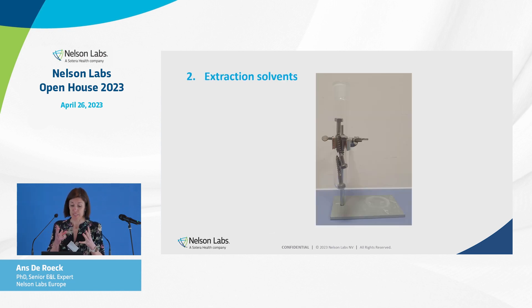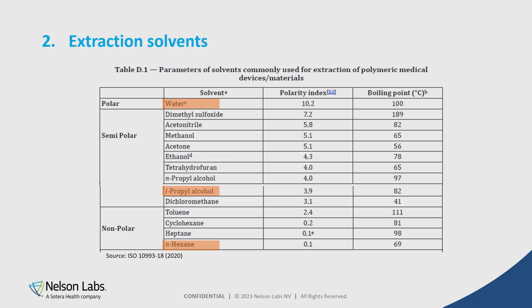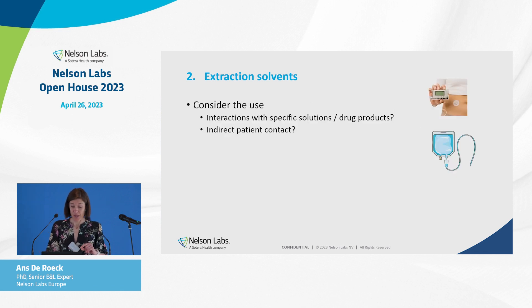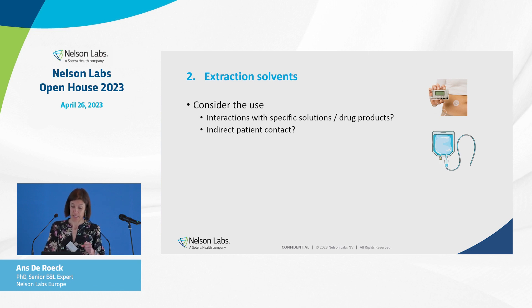We put the test items in a container and add solvents. The guideline says to use two solvents of differing polarity. Most often we use water as a polar solvent and hexane as a non-polar solvent. For blood contact or long-term implants, a third semi-polar solvent like isopropanol can be added. You also have to consider use-specific interactions — you might add an additional solvent — or for indirect patient contact it can suffice to test only one solvent, for example sodium chloride for a saline infusion bag.